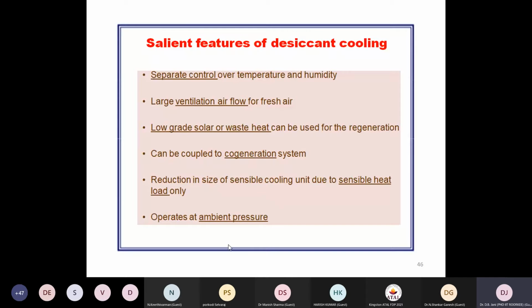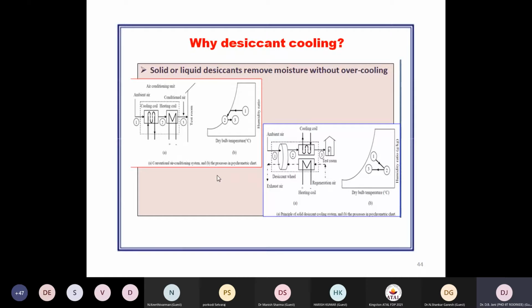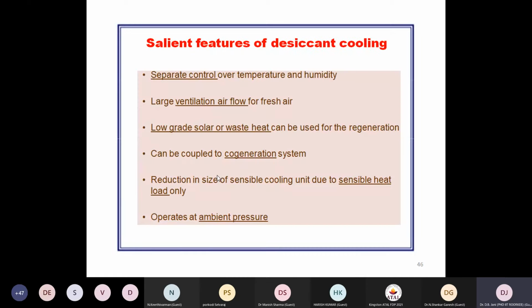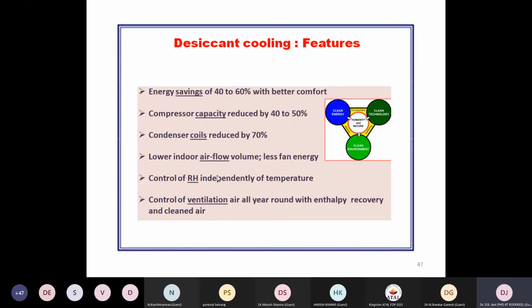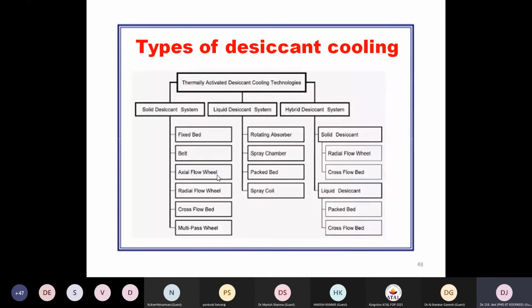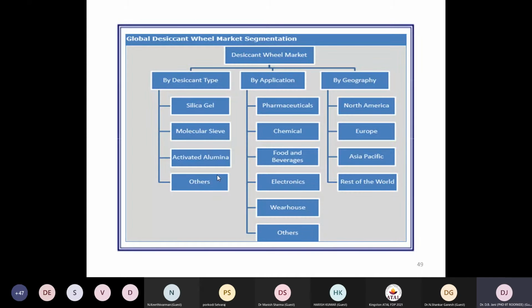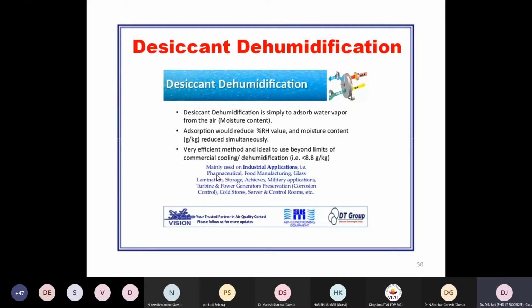Reduce the size of the cooling unit, you can say to one quarter of the total size, as the cooling requirement drops drastically, since the dehumidification task can be taken out separately with the dehumidifier. It almost operates at ambient temperature and pressure. So whatever the use, desiccant cooling can meet the requirement of clean energy, clean technology, as well as a clean environment simultaneously. There are a number of desiccant materials used according to their state as well as the application. There may be silica gel, molecular sieve. Some typical applications were listed; it can be used in any part of the world wherever ambient humidity may be a severe problem.